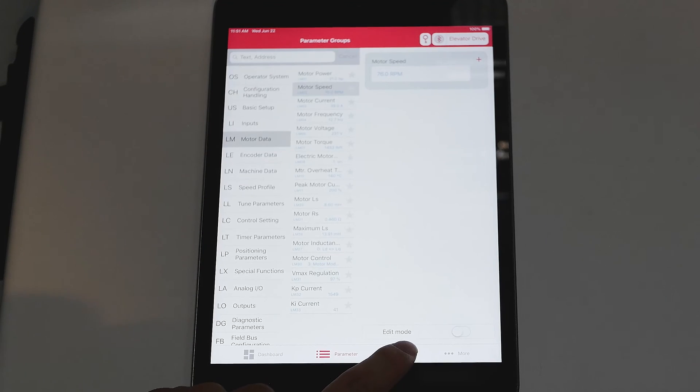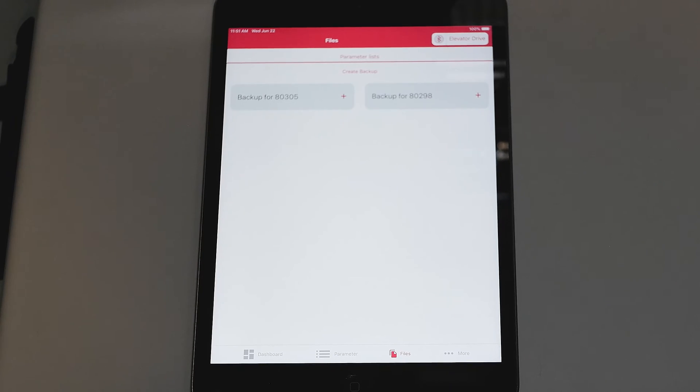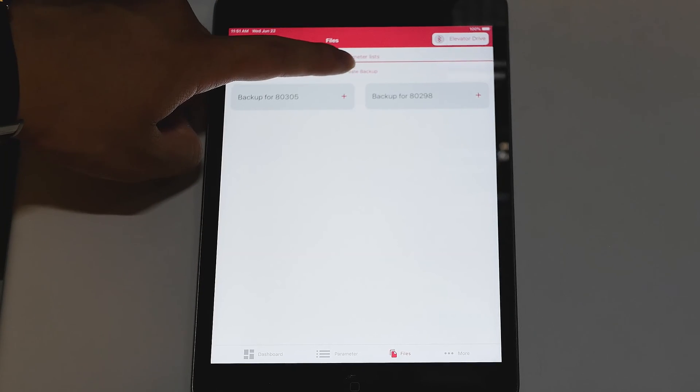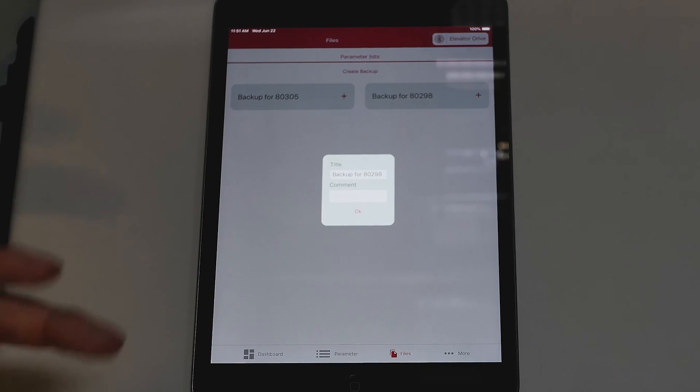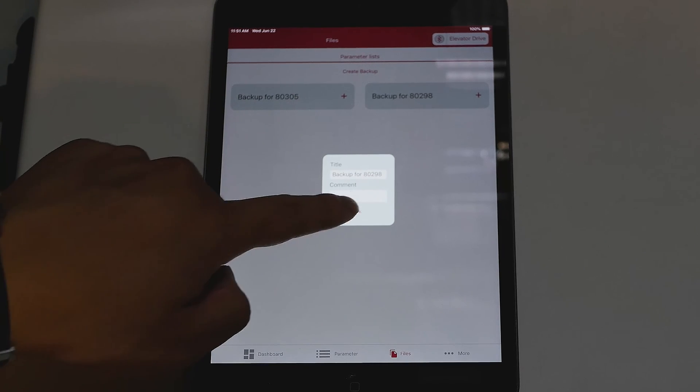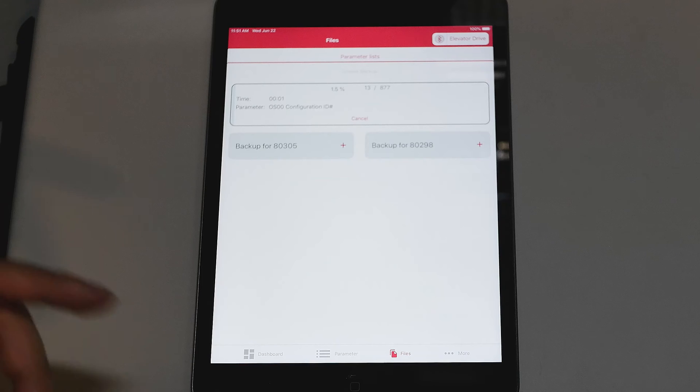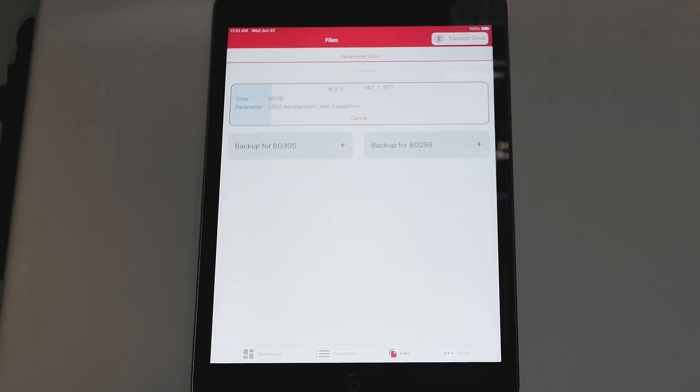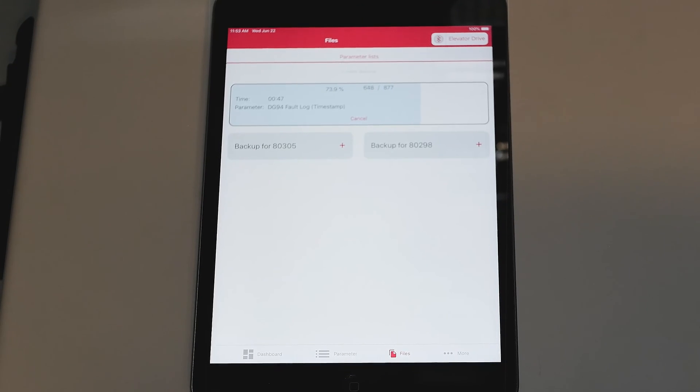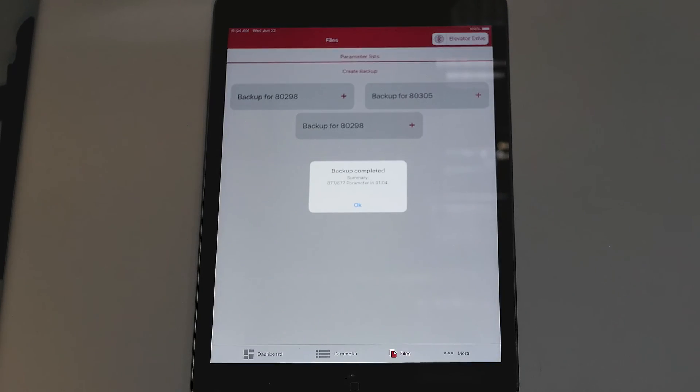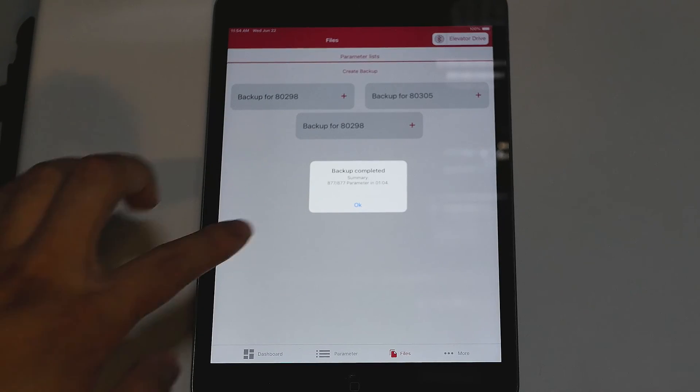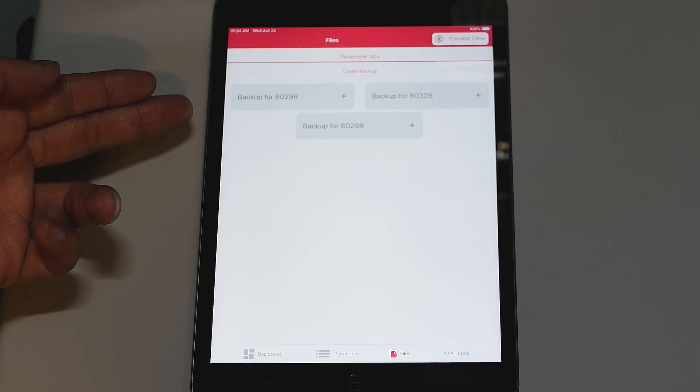You can also make a parameter backup which saves all the parameters on the drive right onto your device. To do so, you click create backup. You would name your title for it could be your job address, job name, car number. Click OK and then it will start writing all the parameters to your Android or Apple device. After your download is complete, it will show backup completed on the screen. You can click OK to remove it from the screen and your backup is now created.